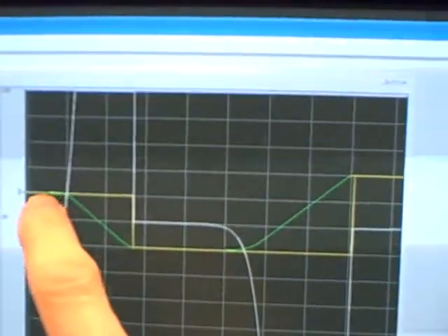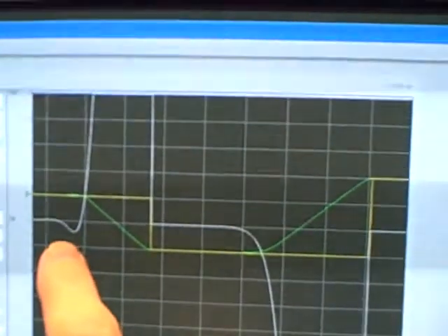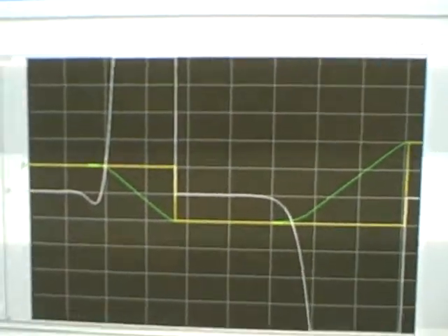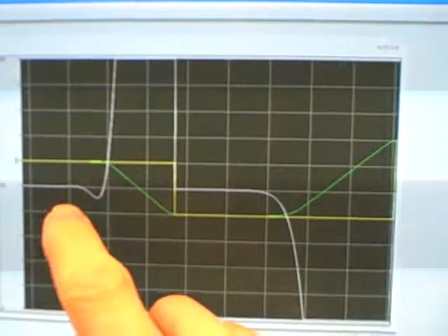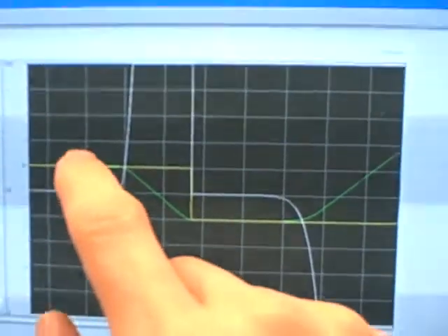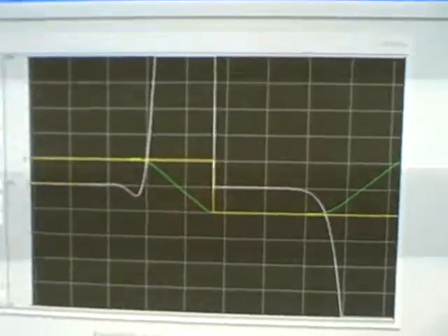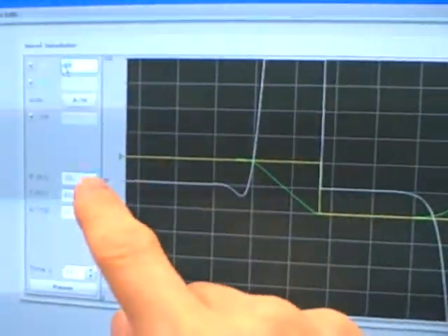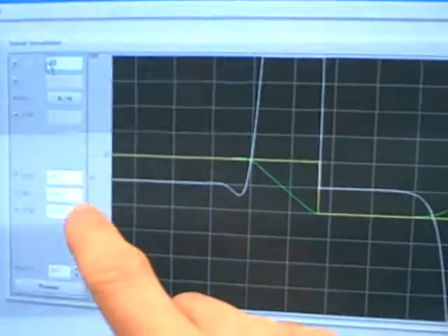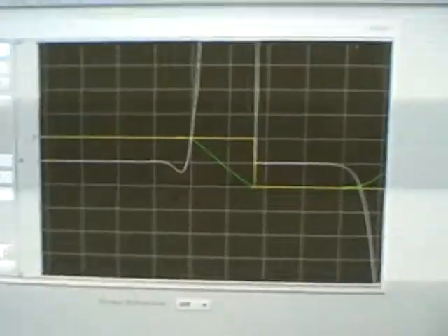The process variable settles right into the new set point value very rapidly, and our valve is right back at 50% where it started. Once again, being an integrating process, putting the valve back at its original equilibrium position means we hold the level wherever we're at. So we see here an integrating process does phenomenally well with a high gain value in the controller with no integral and no derivative action. In fact, integral here would actually hurt us because integral action, when it sees an error, continues to wind the output in one direction or the other. And that in this process would actually guarantee overshoot.